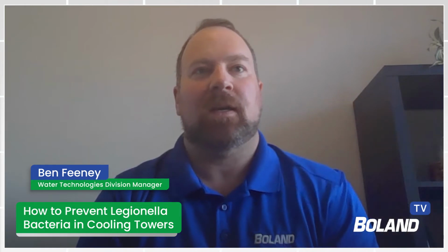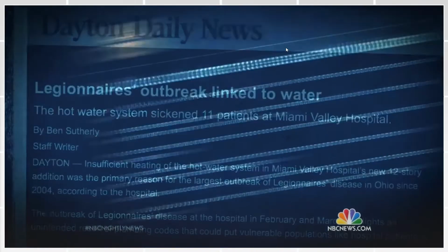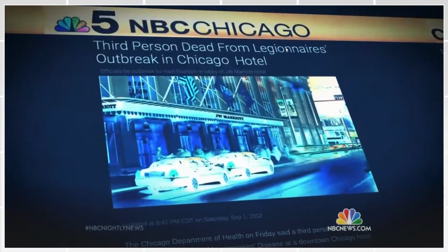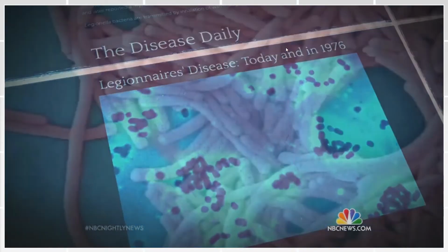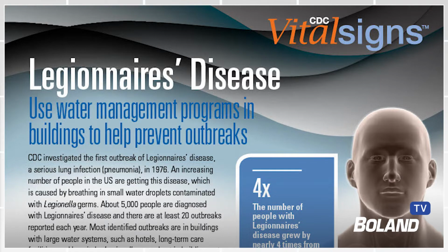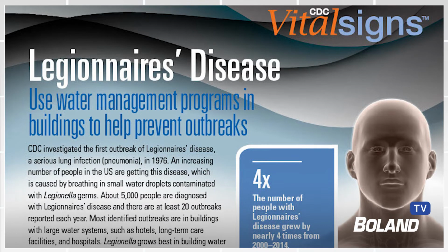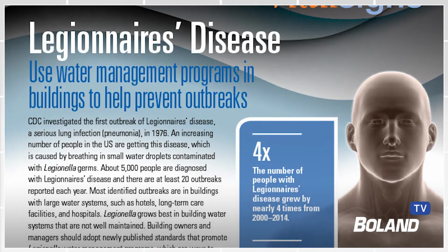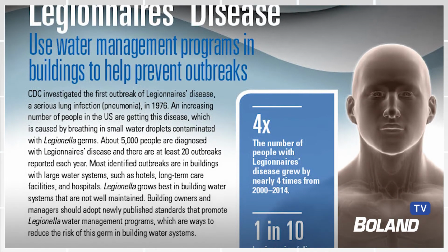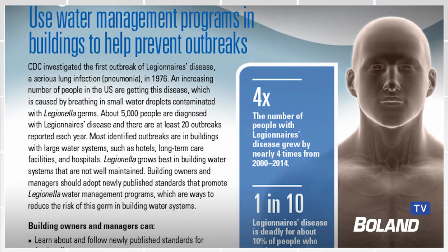As temperatures get into the 70s and higher, upwards to 100 degrees, Legionella thrives. And the amoebas and other bacteria that the Legionella uses as hosts, they tend to survive in those conditions. So starting out with shocking the system, we call it a bulk feed of biocide, just to kill off what's in that cooling tower is definitely recommended.